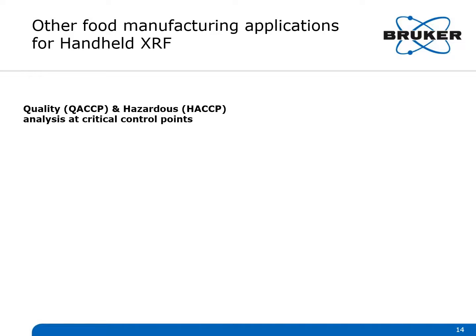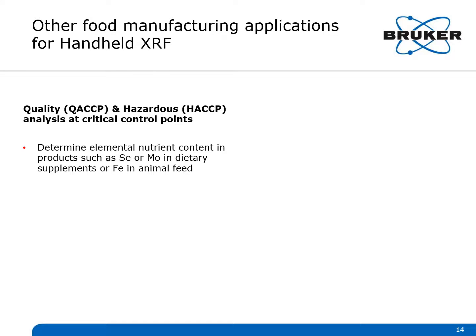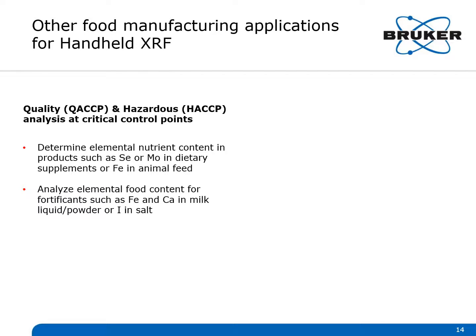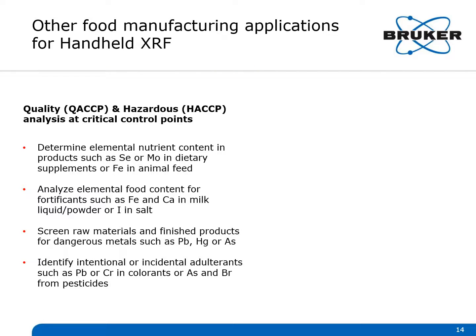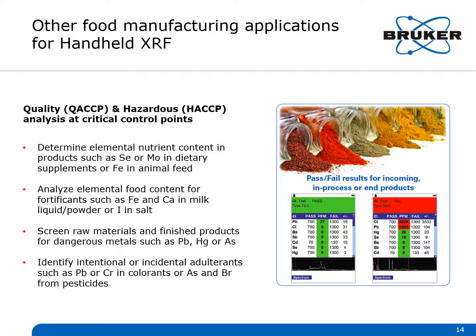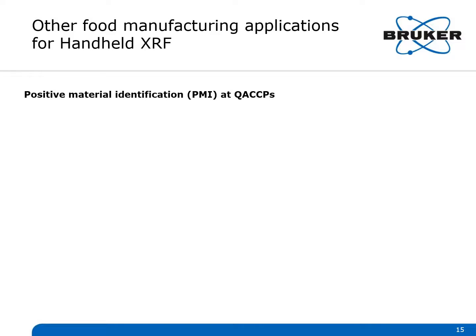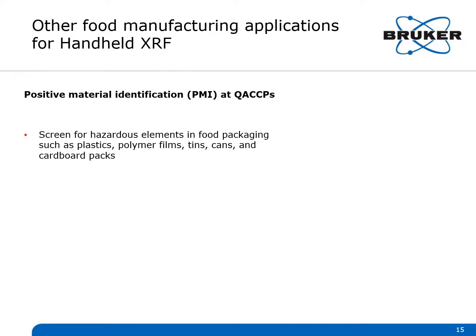There are other food safety applications handheld XRFs work well for. You can determine elemental nutrient content in products such as selenium or molybdenum in dietary supplements, or iron in animal feed. You can analyze elemental food content for fortifications such as iron and calcium in liquid or powdered milk, or iodine in salt. You can screen raw materials and finished products for dangerous elements such as lead, mercury, and arsenic. You can also identify intentional or incidental adulterants such as lead or chromium in colorants, or arsenic and bromine from pesticides. Threshold concentrations can be programmed into the analyzer to indicate simple pass or fail results on the handheld screen. Additionally, you can screen for hazardous elements in food packaging such as plastics, polymer films, tin cans, and cardboard packs.